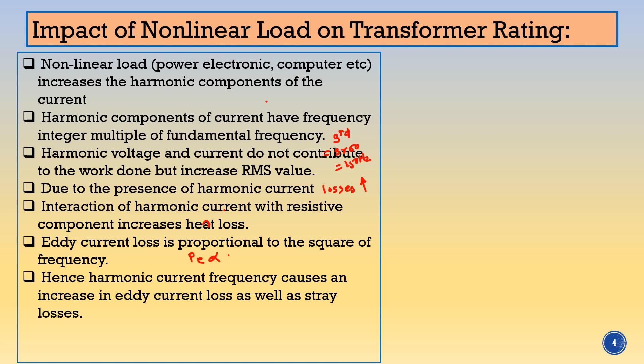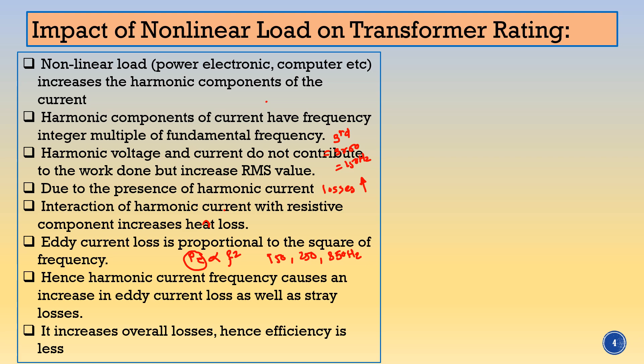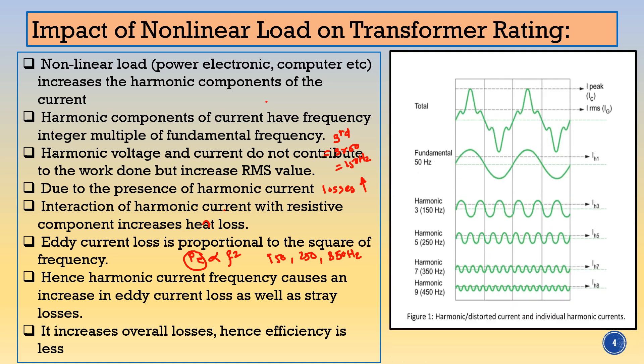If we denote eddy current loss as PE, then PE is proportional to frequency squared. The third harmonic has a frequency of 150 Hz, the fifth harmonic has 250 Hz, and the seventh harmonic has 350 Hz. As the frequency goes on increasing, the eddy current component loss also goes on increasing. Hence harmonic current causes increases in eddy current loss as well as stray losses, increasing the overall losses. Hence the efficiency of the transformer will decrease.